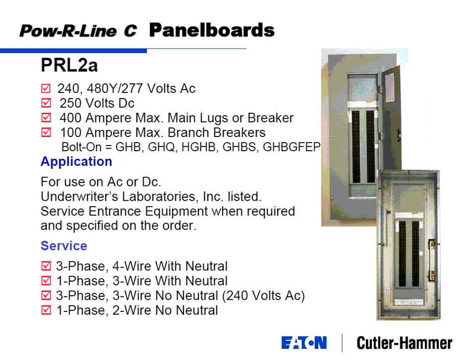Powerline 2 panel boards are very similar to Powerline 1 panel boards, except the big difference is the voltage. So Powerline 1 panel board is 208 volts, Powerline 2 panel board is 480 volts. And they'll both be 400 amps, and the branch circuit breaker style is the GHB or GHQ. Looks the same. Same type of breakers. Both breakers will look about like this, but one will be 480 rated and the other will be 208 volt rated.